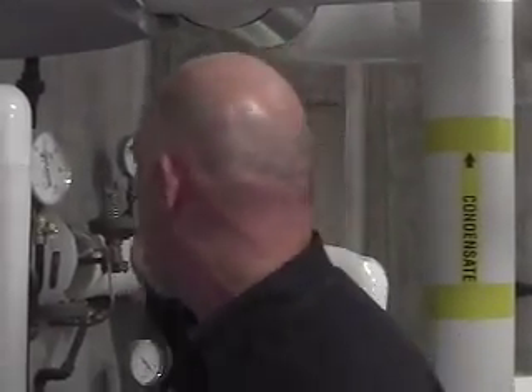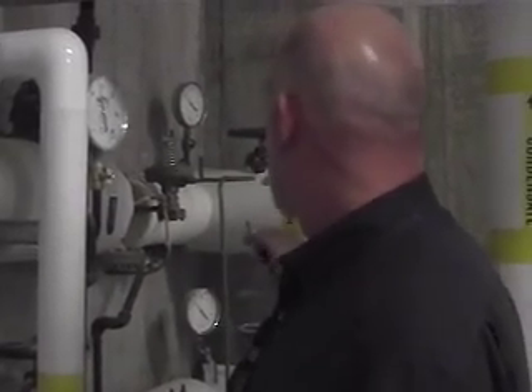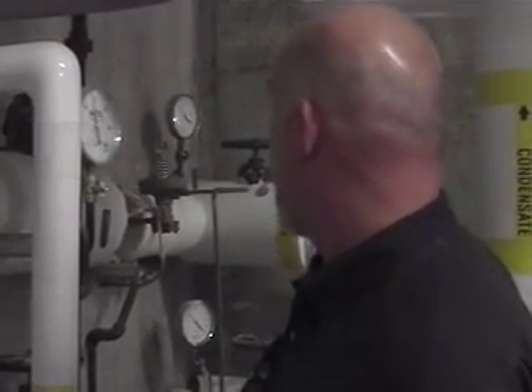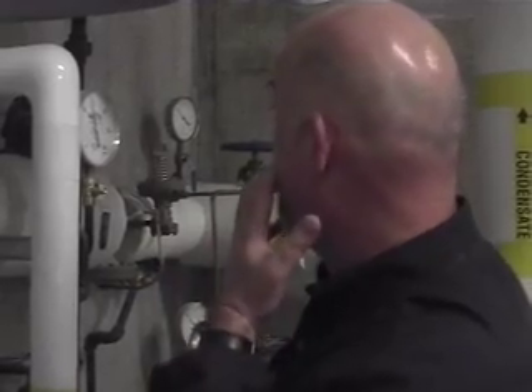Yeah, this thing is set for 25 PSI. So the only way this thing is going to pop off is if these PRVs aren't working, if the head pressure went up past 20. These would have to fail. Or one of these valves has to shut too fast. This top one? Yeah. Well, maybe the electronic valve fails too fast, that's what builds pressure instead of that.